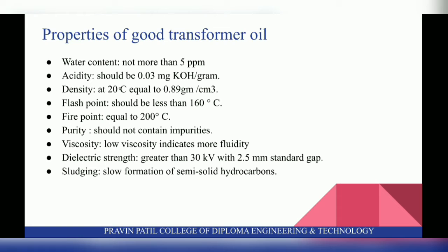Next is the fire point. Fire point is the temperature at which the oil will ignite and continue burning. So fire point should be about 200 degrees Celsius. Next is purity. It should not contain impurities such as sulfur and its compound. It causes corrosion of metal parts and accelerates formation of sludge.